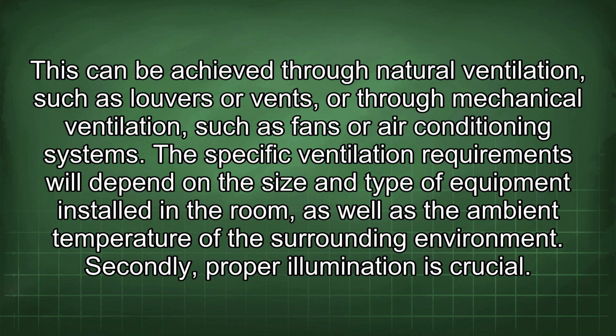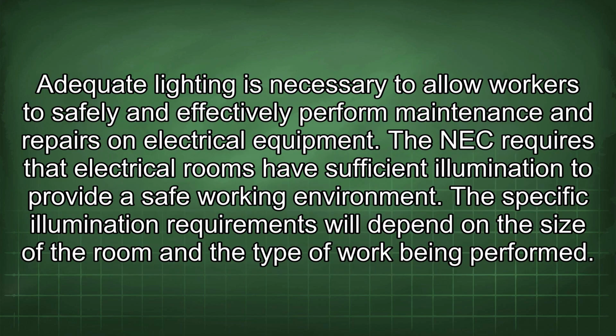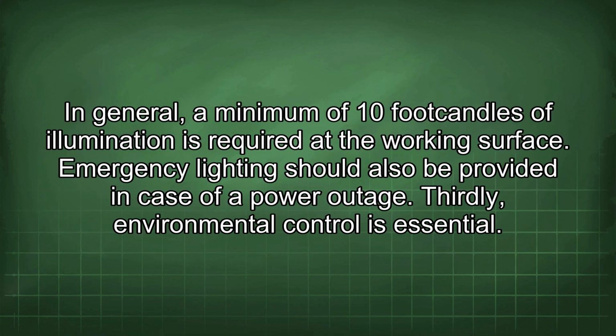Secondly, proper illumination is crucial. Adequate lighting is necessary to allow workers to safely and effectively perform maintenance and repairs on electrical equipment. The NEC requires that electrical rooms have sufficient illumination to provide a safe working environment. The specific illumination requirements will depend on the size of the room and the type of work being performed. In general, a minimum of 10 footcandles of illumination is required at the working surface. Emergency lighting should also be provided in case of a power outage.